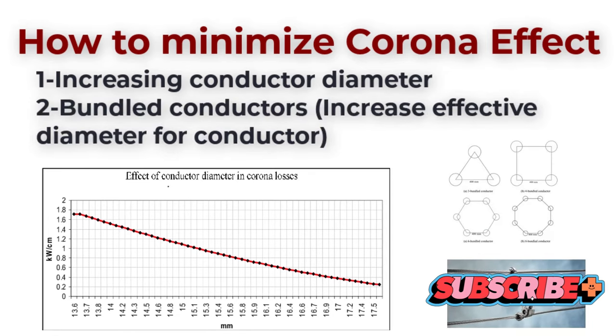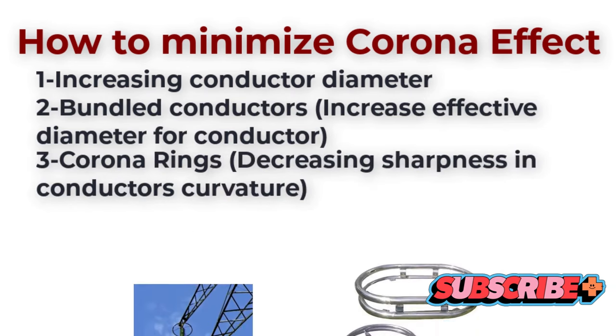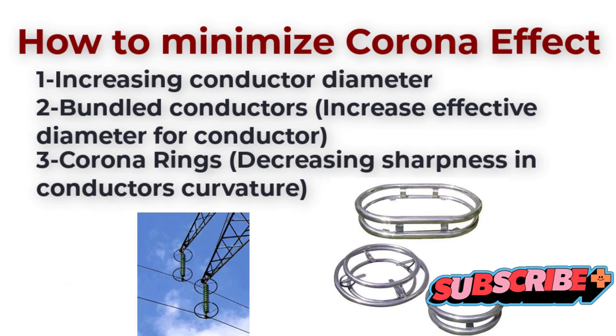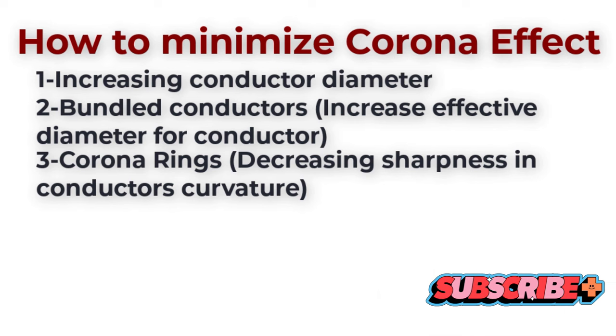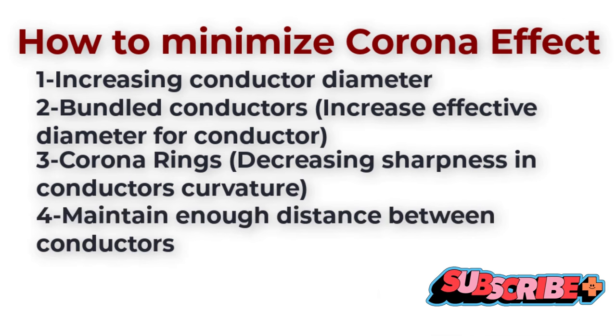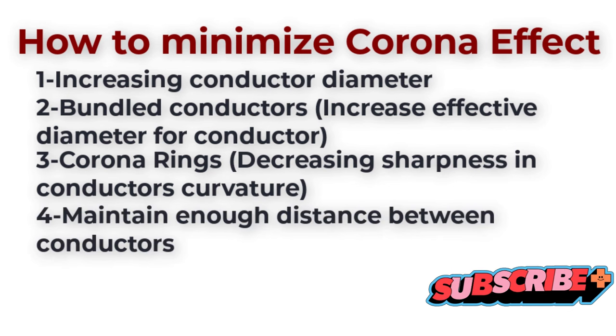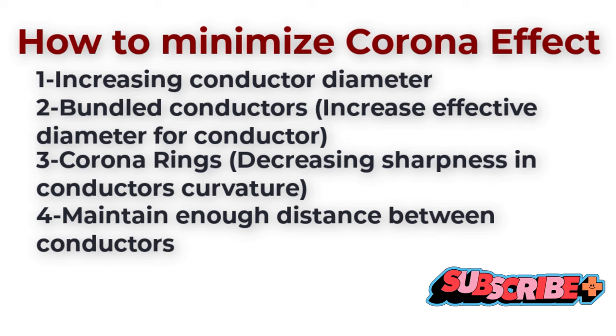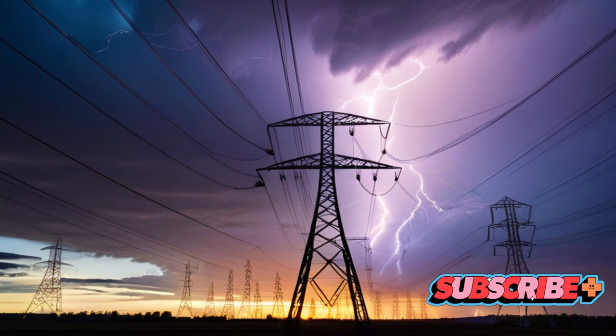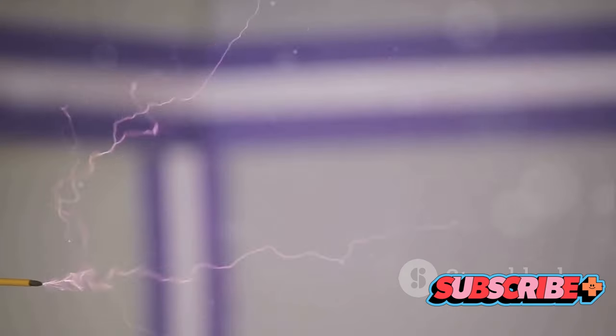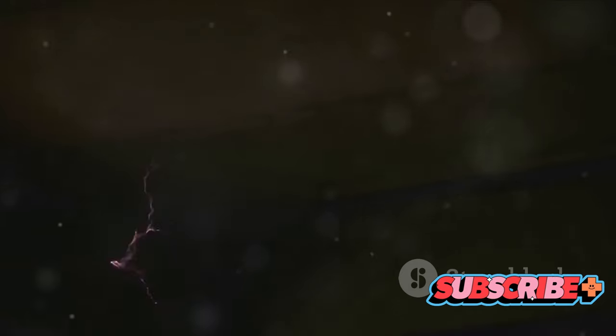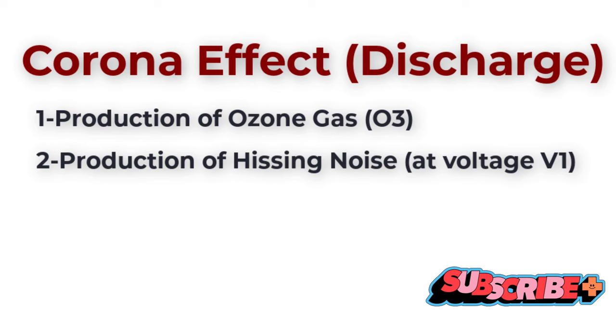Wrapping up, corona discharge is a fascinating yet complex phenomenon in the electrical world. It's a process where the air around a conductor becomes ionized and electrically conductive, causing the conductor to glow. This occurs when the electric field strength is high enough to ionize the air but not high enough to cause electrical breakdown or arcing to nearby objects. Corona discharge can occur in high voltage systems, particularly where sharp points, edges, or uneven surfaces are present on the conductor, and is more likely under wet or humid conditions and at higher altitudes where the air is thin.